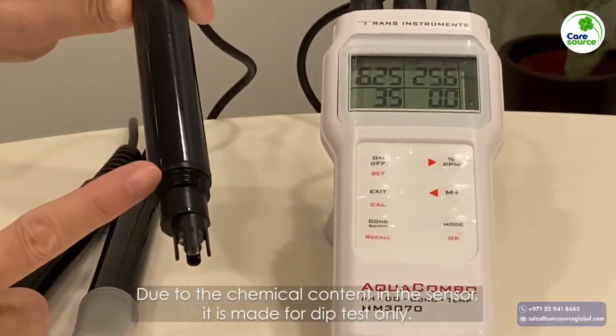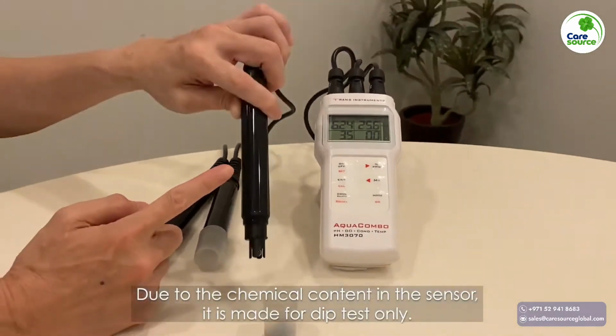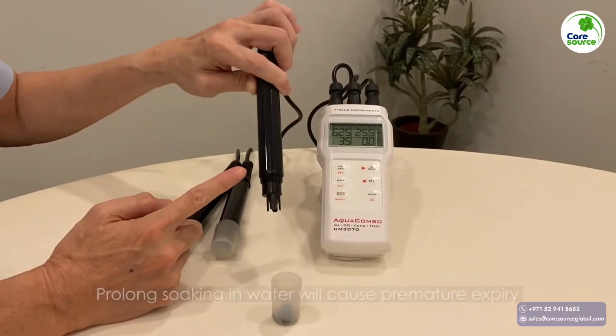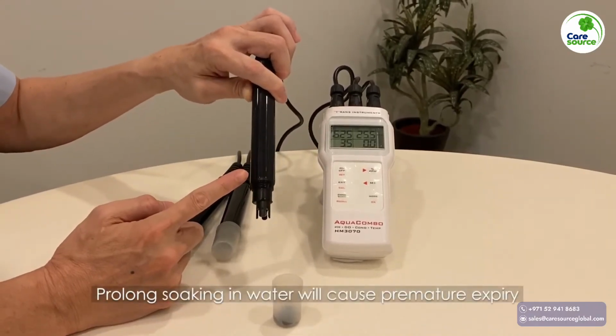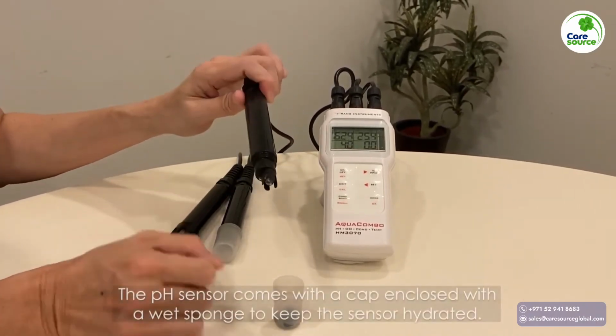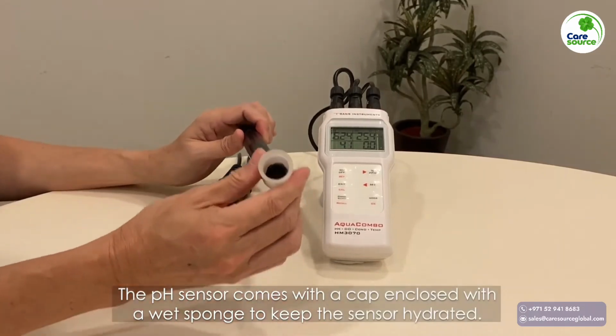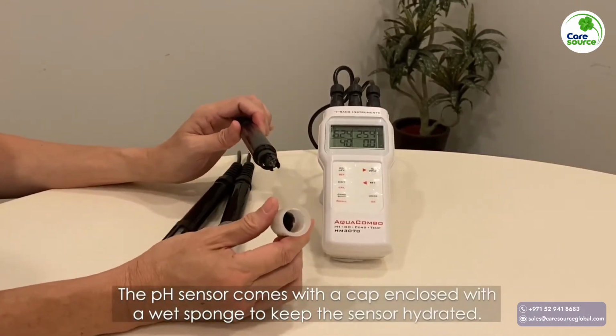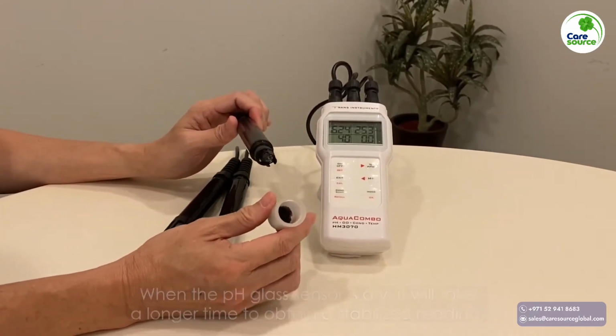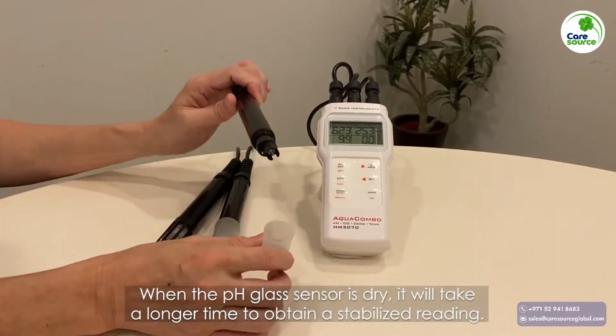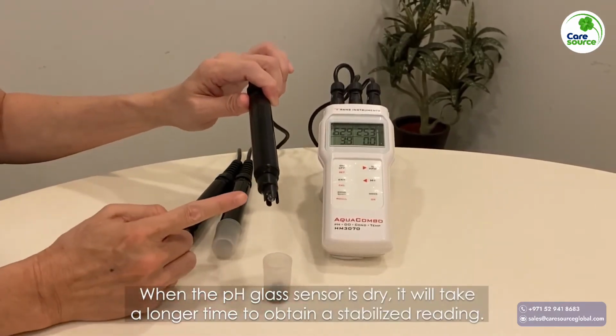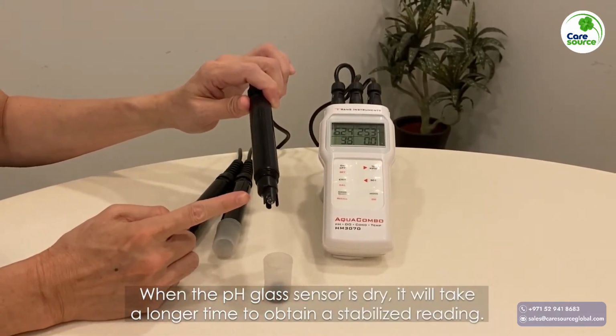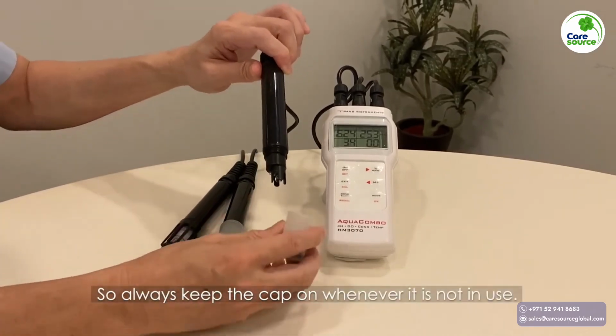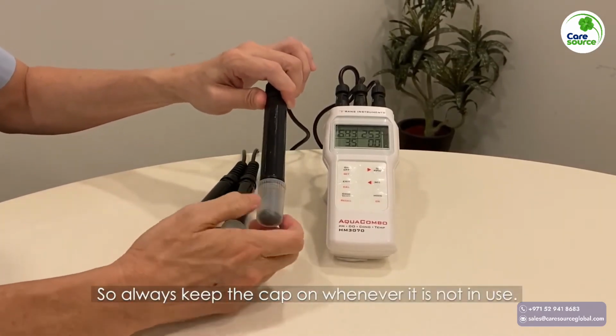Due to the chemical content in the sensor, it is made for dip test only. Prolonged soaking in water will cause premature expiry. The pH sensor comes with a cap enclosed with a wet sponge to keep the sensor hydrated. When the pH glass sensor is dry, it will take a longer time to obtain a stabilized reading. So always keep the cap on whenever not in use.